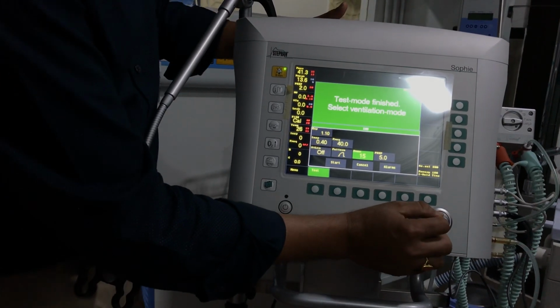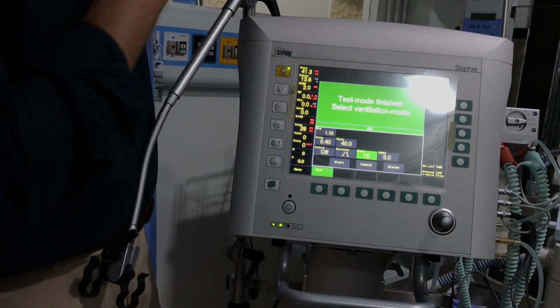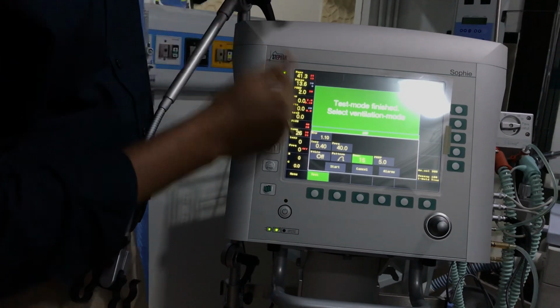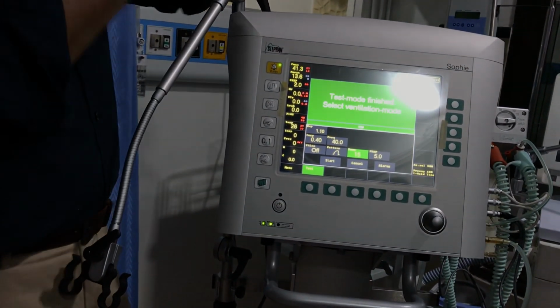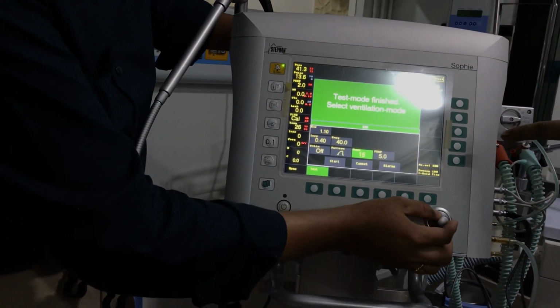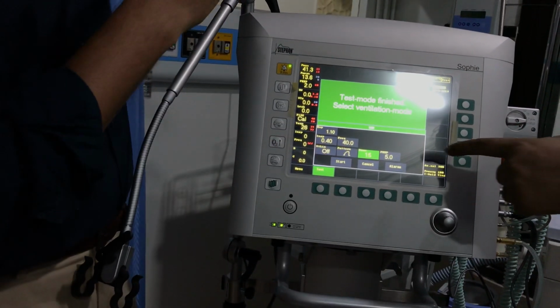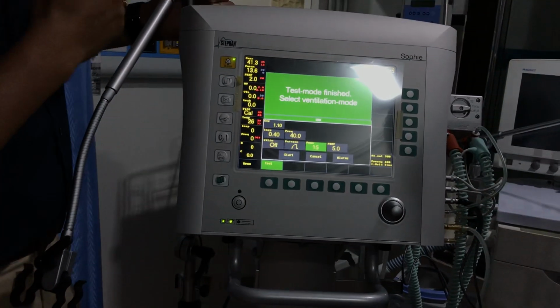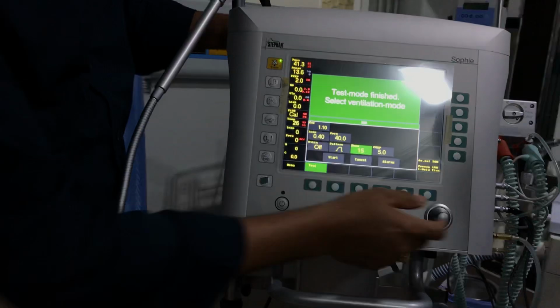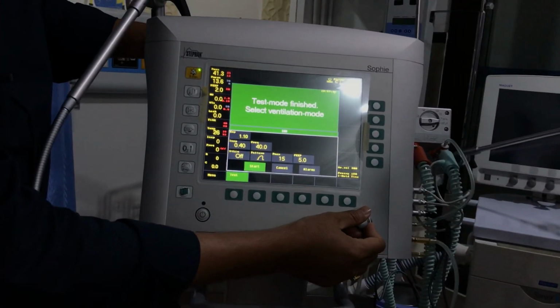This is the P max. That includes your PEEP, sir. This is the maximum inspiratory pressure. Some ventilators have a PIP. Yeah, it's a PIP in short, but it includes PEEP. So the PC above PEEP will be 10 plus 5. Yes, the delta pressure is 10. This is PEEP, and then I will go to start.